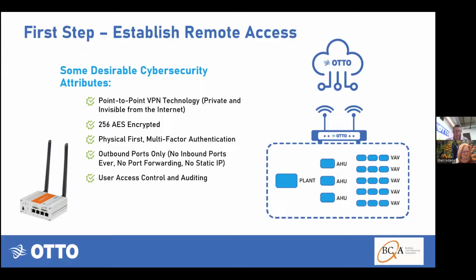Another thing to keep in mind is that functional testing isn't supposed to start until the contractor says, and the commissioning provider agrees, that pre-functional testing has occurred—including safeties and alarms, that type of stuff. So there are layers of protection in any project, OTTO involved or not, and it's a discussion that needs to be had.